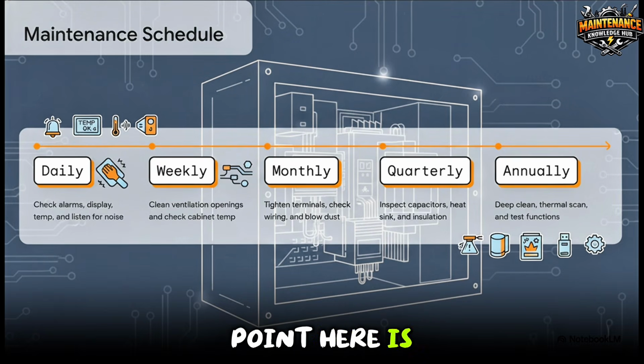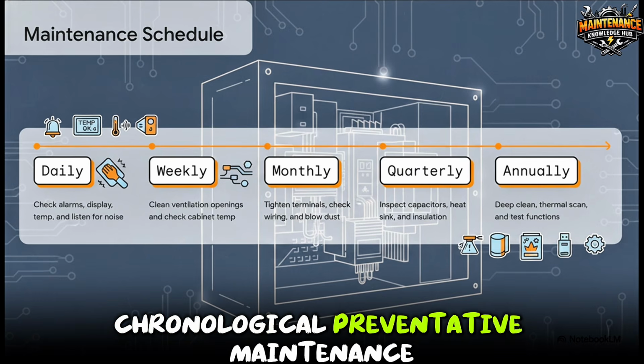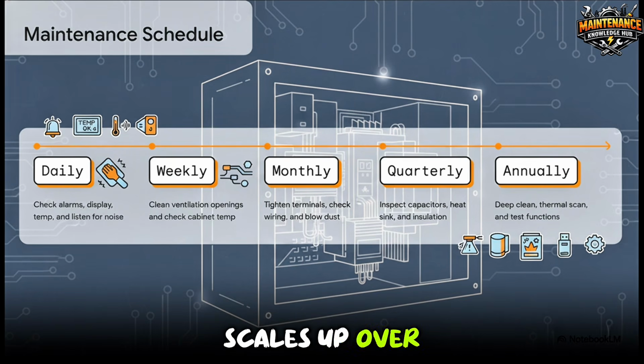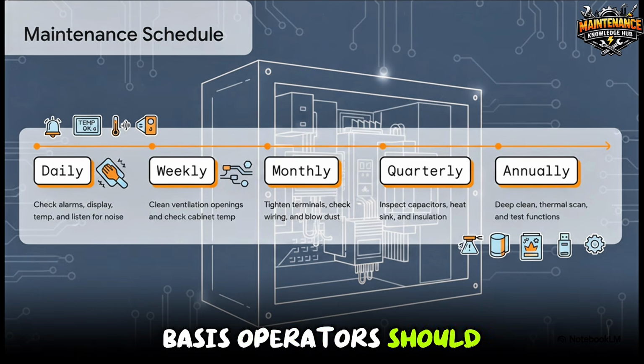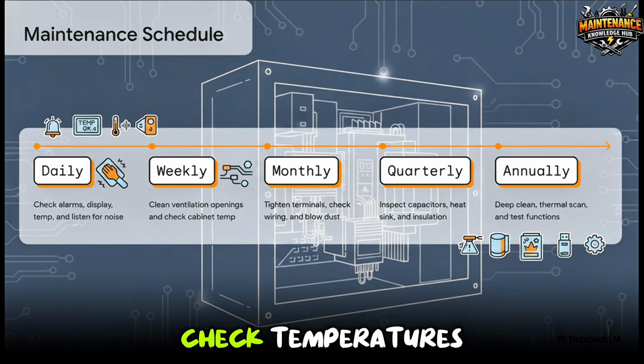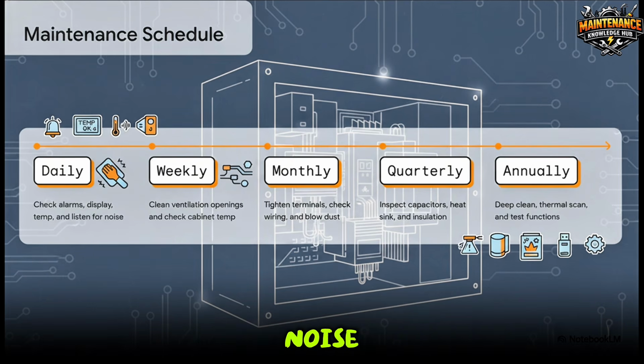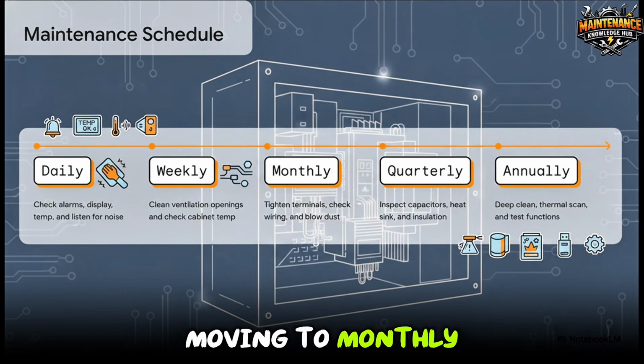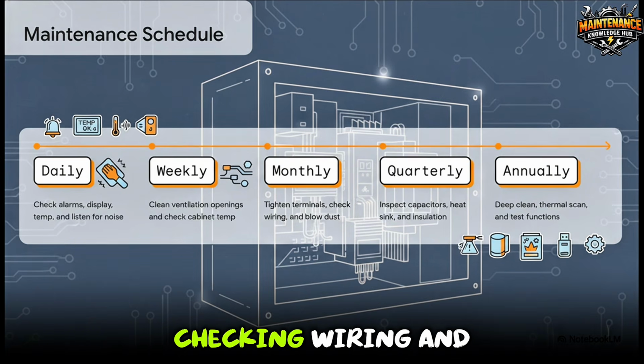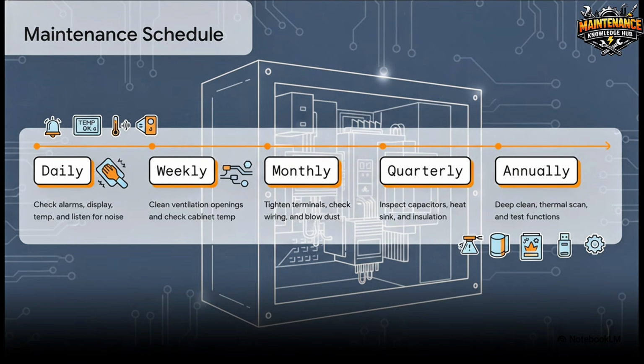So the crucial point here is establishing a proper, chronological, preventative maintenance schedule, and it really scales up over time. On a daily basis, operators should just check alarms, observe the display, check temperatures, and just listen for any unusual noise. Weekly, the focus shifts to cleaning vents and checking cabinet temps. Moving to monthly, you're physically tightening those power terminals, checking wiring and grounding, and blowing out dust. Then, quarterly, it gets a bit more intense, thoroughly inspecting the capacitors and heat sinks, and measuring insulation resistance with the motor disconnected.